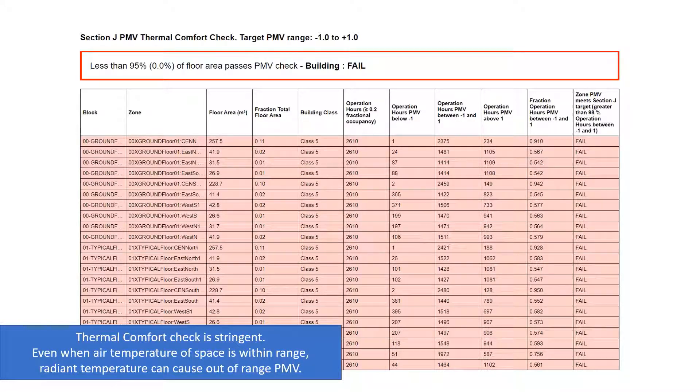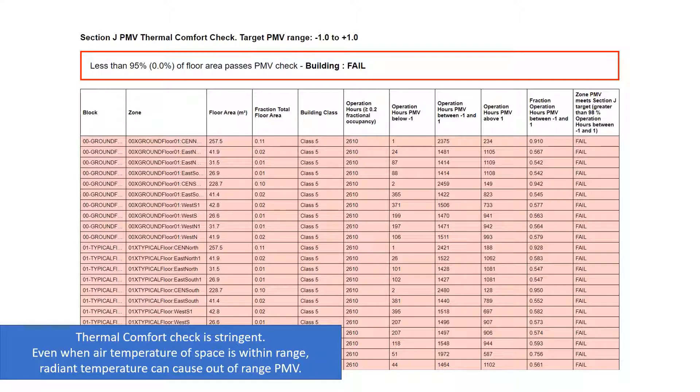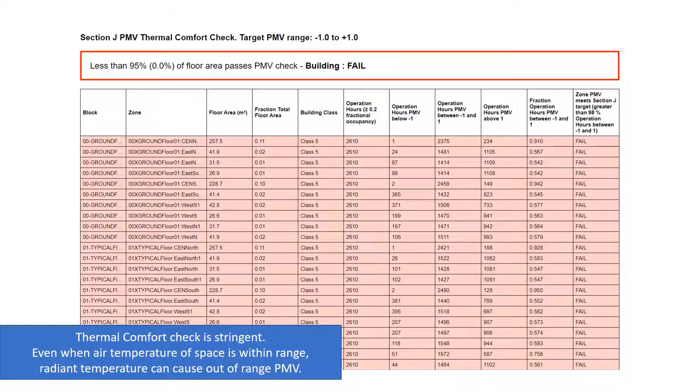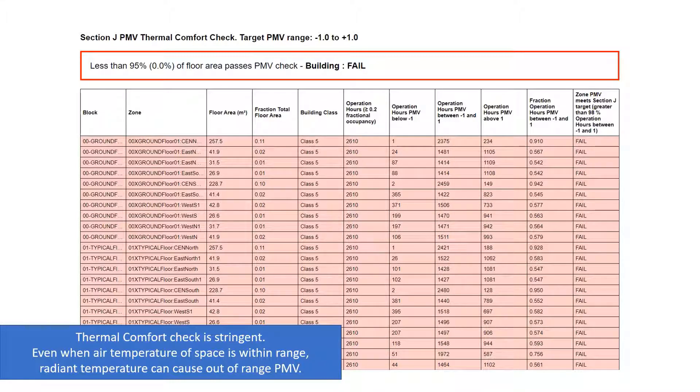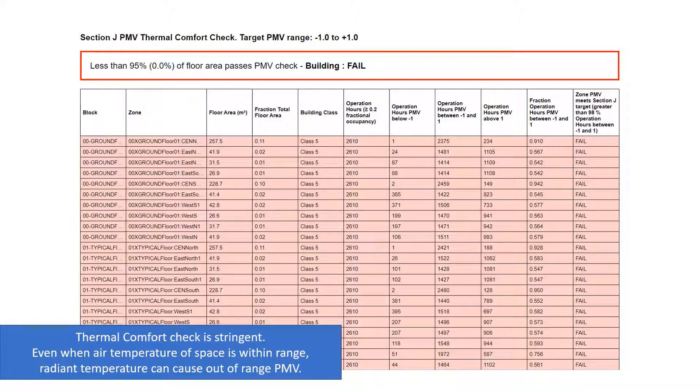The comfort check is quite stringent. If the report shows an unexpectedly large number of occupied hours where the thermal comfort values are outside the target range, even though the temperature is controlled, you may be seeing a large contribution from the radiant temperature of the space. This is most likely in highly glazed spaces. Design modifications may be required.